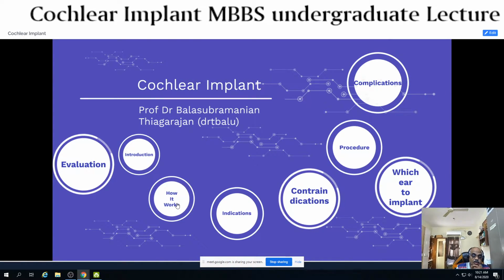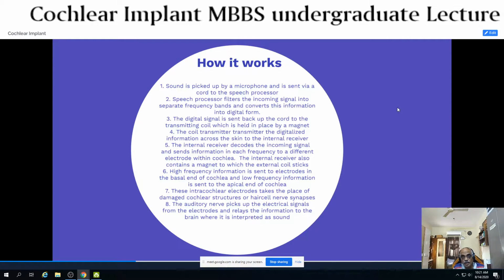How exactly does this cochlear implant work? Sound is picked up by the microphone present in the outer unit, and then this sound is sent to the speech processor via a small connecting cable. This speech processor has a unique role to play. It is an auditory filter. It filters the incoming sound signals into different frequencies, and it also digitalizes the analog sound into digital sound. In other words, it converts the sound energy into electrical energy. So it digitalizes the auditory potential into electrical potential.